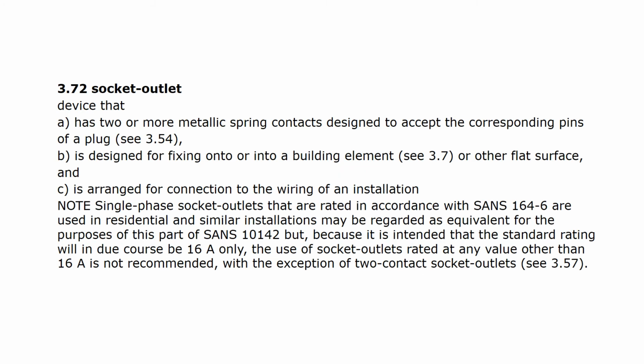Socket outlet: device that has two or more metallic spring contacts designed to accept the corresponding pins of a plug, is designed for fixing onto or into a building element or other flat surface, and is arranged for connection to the wiring of an installation. Note, single-phase socket outlets that are rated in accordance with SANS 164-6 and are used in residential and similar installations may be regarded as equivalent for the purposes of this part of SANS 10142, but because it is intended that the standard rating will in due course be 16 amps only, the use of socket outlets rated at any value other than 16 amps is not recommended, with the exception of two contact socket outlets.